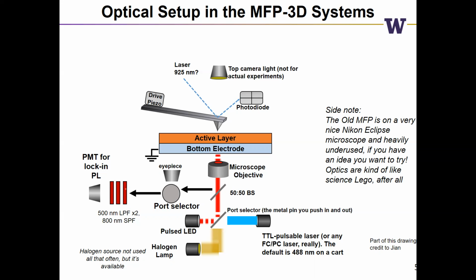That goes through a set of filters. There are two 500 nanometer long pass filters and an 800 nanometer short pass filter. If you need other filters, we actually do need to buy more. This is a good reminder if you want to use a 405 as an excitation source or whatever. But either way, these can route into the PMT that's sitting there. That lets you do a lock-in photoluminescence measurement, so you can correlate PL with your AFM measurement.